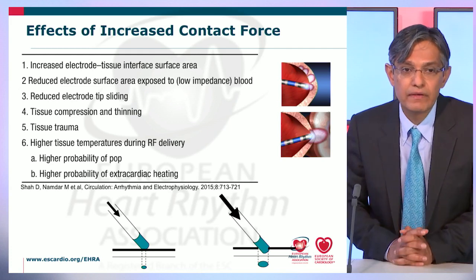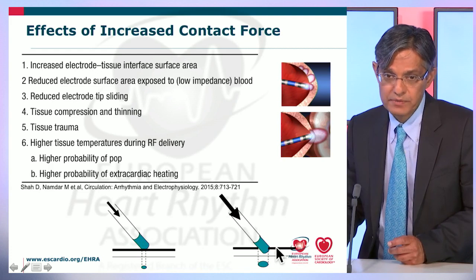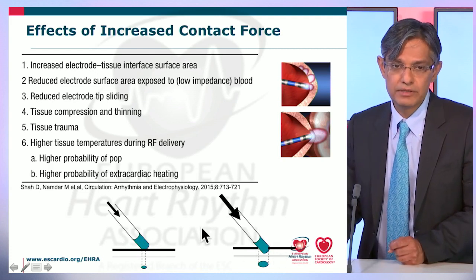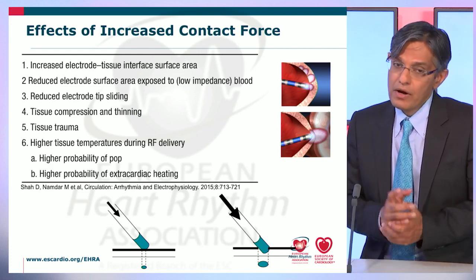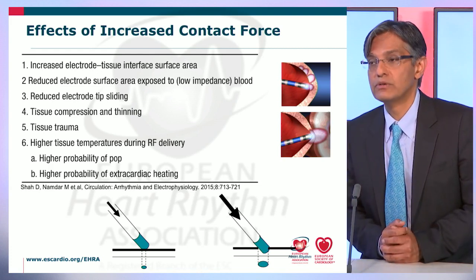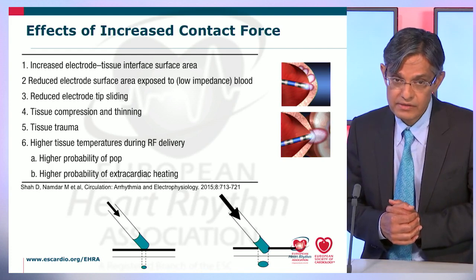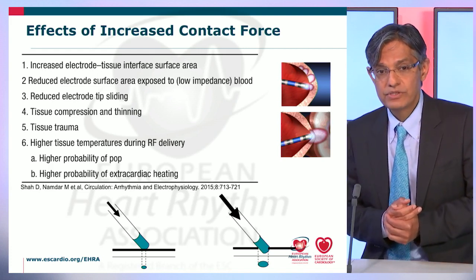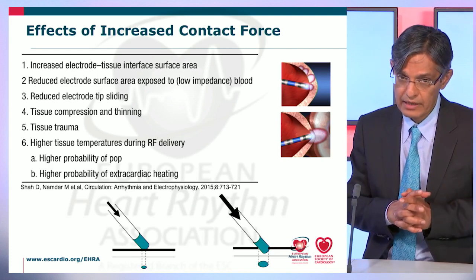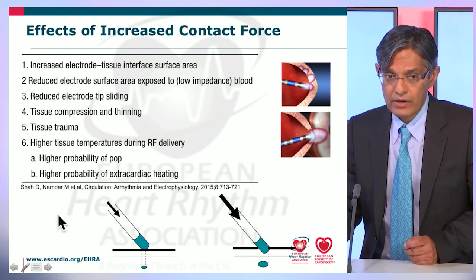To summarize the effects of increased contact force: increased electrode-tissue interface surface area as the electrode gets buried into soft atrial or ventricular myocardial tissue; reduced electrode surface area exposed to low-impedance blood; reduced electrode tip sliding in response to respiratory and cardiac movement; tissue compression and thinning; tissue trauma; higher tissue temperatures during RF delivery; and therefore a higher probability of steam pop and extra-cardiac heating.